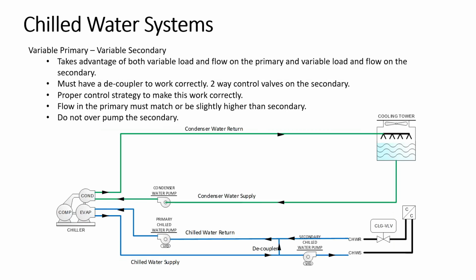Now this is the ultimate of everything, a variable primary along with a variable secondary. Both of these systems, the constant primary and the variable secondary, have issues that the operators may or may not understand. And so we're always constantly running into issues where they are complaining that something's wrong. This system, the variable primary and the variable secondary, takes advantage of all the benefits you can get out of the chiller. Chiller can operate at a low load. Some of them can go all the way down to 10%. You can vary the flow on the primary down to that low, and you can vary the flow on the secondary. So everything you've got involved is saving energy by reducing the amount of energy you need to operate. So it can match the load on the primary to the load on the secondary.